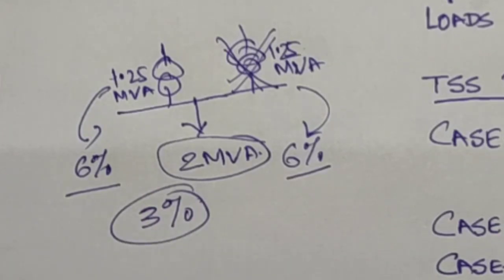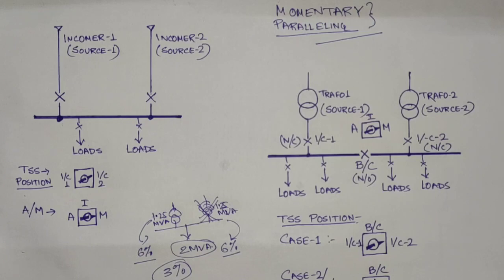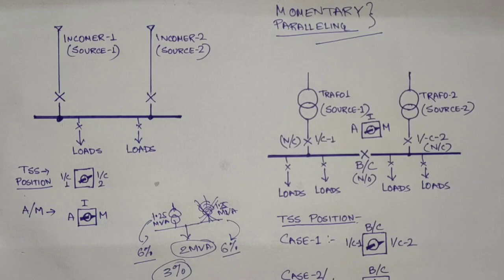Distribution level means at low power levels — 2.5 MVA, 3.15 MVA, or at HV level, maybe 20, 25, or 30 MVA. At the transmission level, where generators are connected with generator transformers, continuous parallel operation is done. But at the lower distribution level, inside a plant distribution, continuous paralleling is not generally used. Instead, momentary paralleling is used.